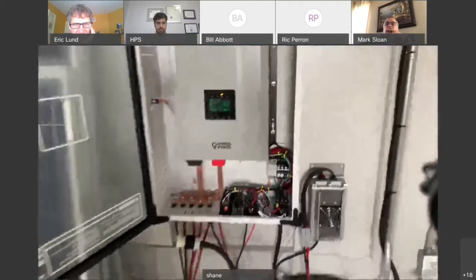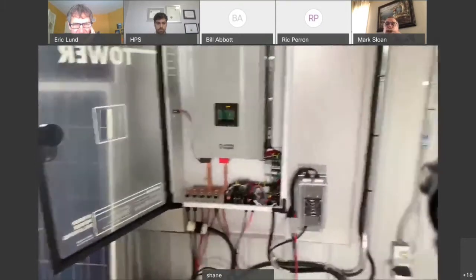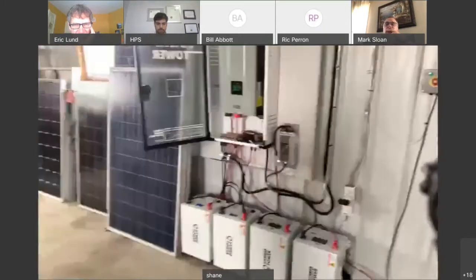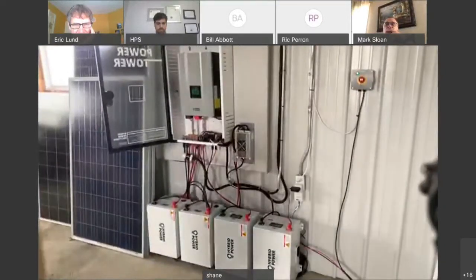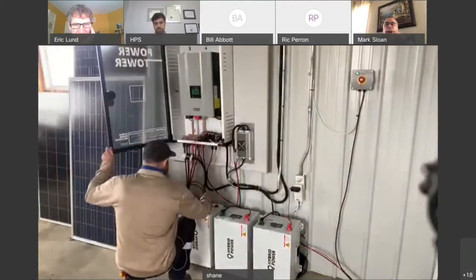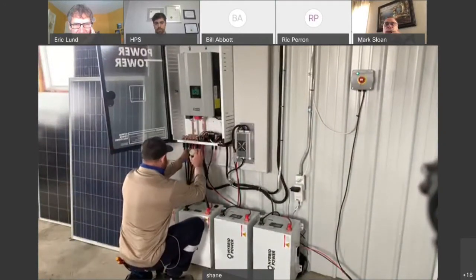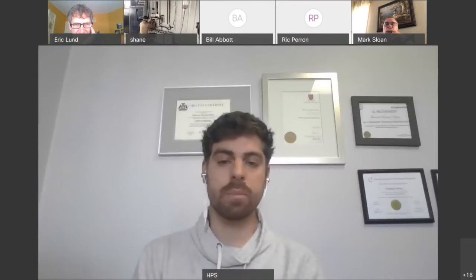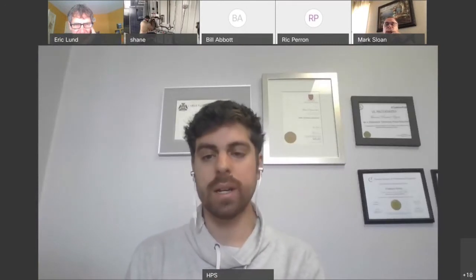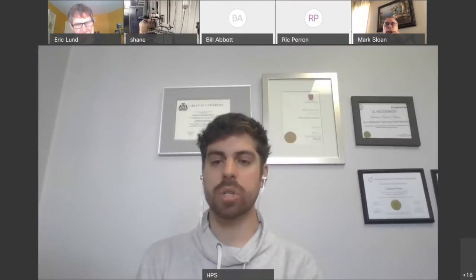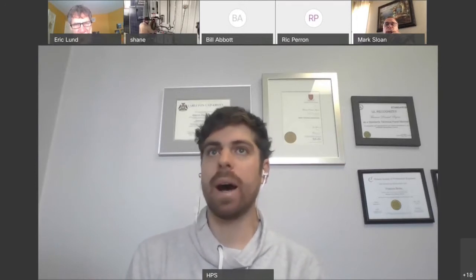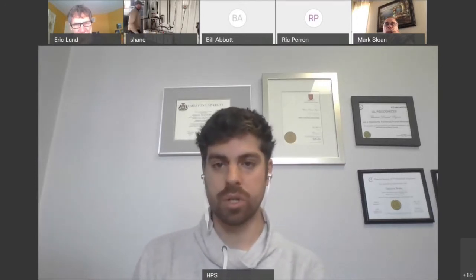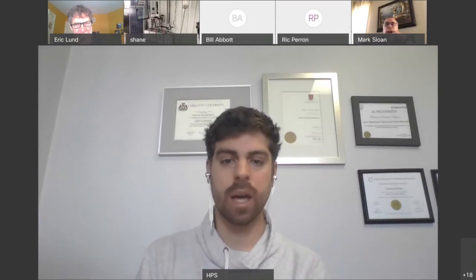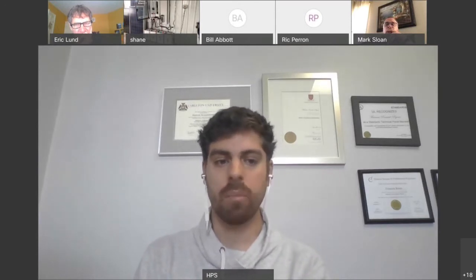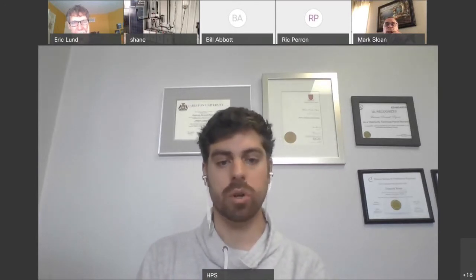So if you're to do what we have here, we have 4 batteries in parallel. See them there. I'll just energize them all. Now, just to mention that obviously before you've energized all 4 of them or any kind of units in parallel, just make sure that you're doing that balancing to make sure that all the voltages are identical. That's going to help you get better performance out of the unit, but it's also going to make sure that you don't have a huge surge between batteries.